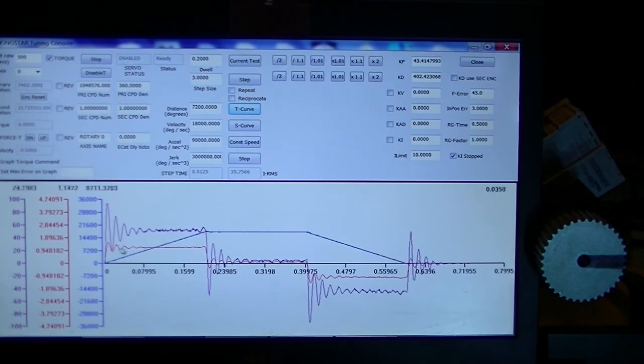And this is the instantaneous following error at every point in time. And the rate that we're running right now is shown up here, EtherCAT rate, microseconds. This is 500 microseconds. So every tick of our EtherCAT network is 500 microseconds. And every 500 microseconds, we pick a new commanded position to get this velocity where we want it. And this is the instantaneous error as we make that move.